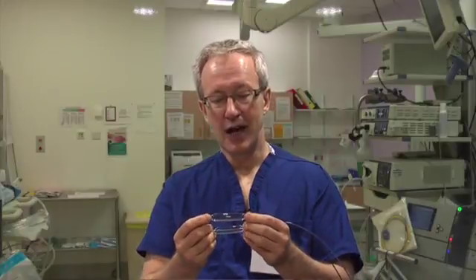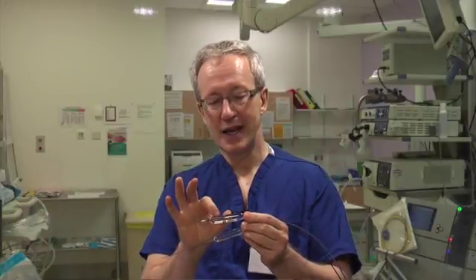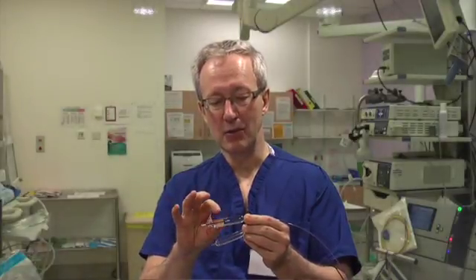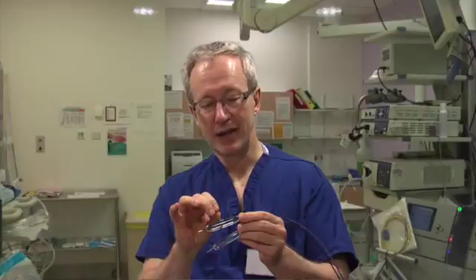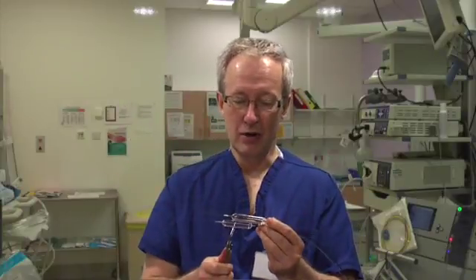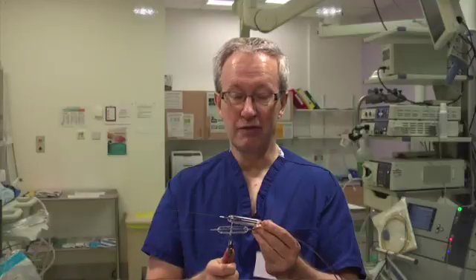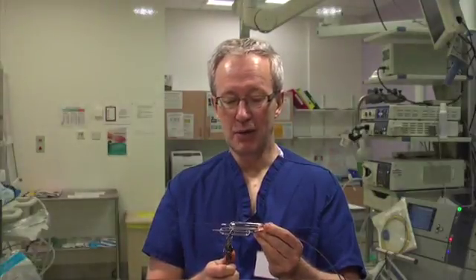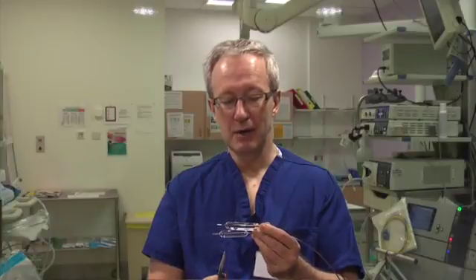The Olympus device has got a nice little trick here. It's got a white segment in the middle, in the center of the dilatation balloon, and you can see that through the balloon, and you can then tell that the middle of the dilator is in the middle of the stricture, and you're doing a good job. Now, feeling the two balloons, they're very similar firmness at full inflation, and we're using a caliper. When I measure the size of the balloons at full inflation pressure, where there should be 15mm, this particular one, I measured the Boston Scientific CRE balloon at 14.8mm, and I measured the Olympus balloon at 15.2mm. It's virtually the same, isn't it?